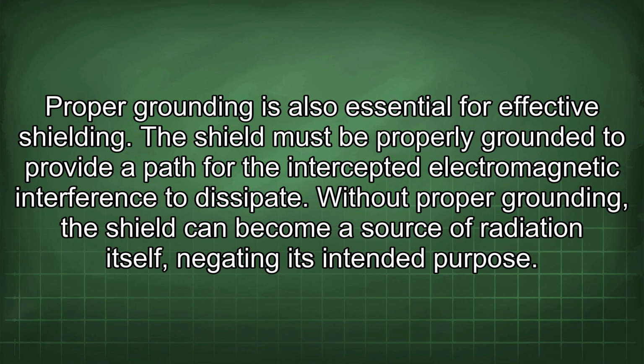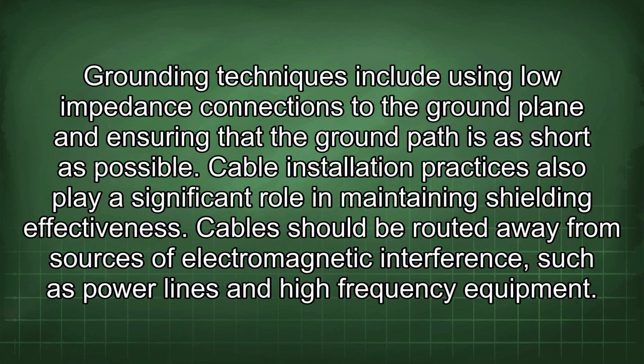Proper grounding is also essential for effective shielding. The shield must be properly grounded to provide a path for the intercepted electromagnetic interference to dissipate. Without proper grounding, the shield can become a source of radiation itself, negating its intended purpose. Grounding techniques include using low impedance connections to the ground plane and ensuring that the ground path is as short as possible. Cable installation practices also play a significant role in maintaining shielding effectiveness.